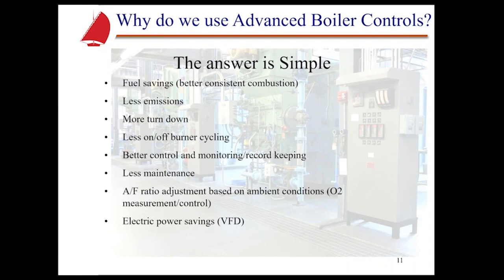And with this type of system, the air-fuel ratio adjustment can be based off of ambient conditions. In other words, it can adjust itself. That's where the O2 trim that we will be talking about comes into play. It is a huge advantage when we start having seasonal changes.